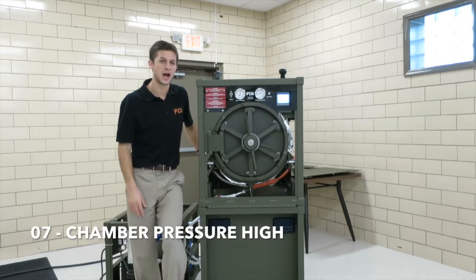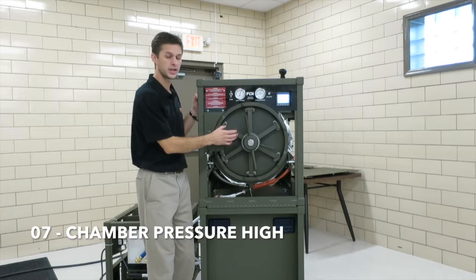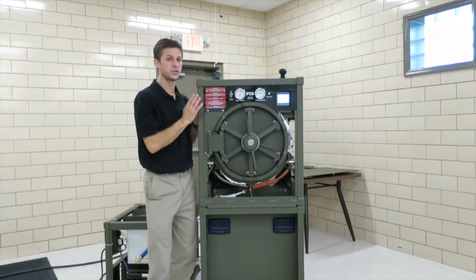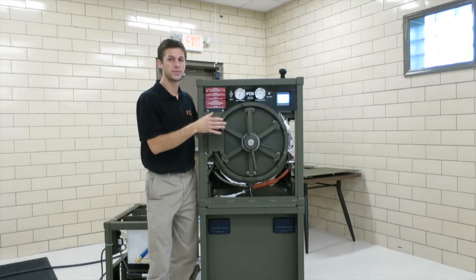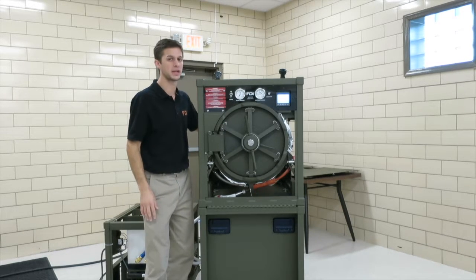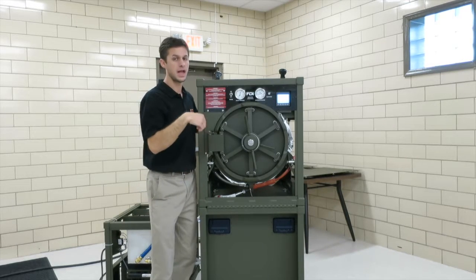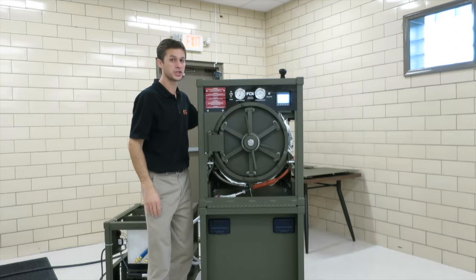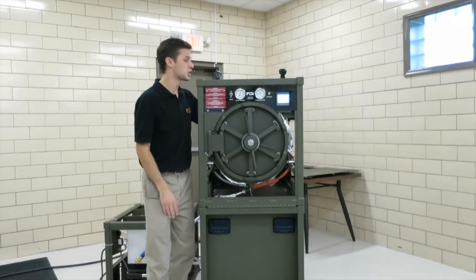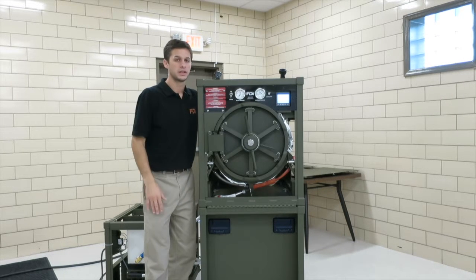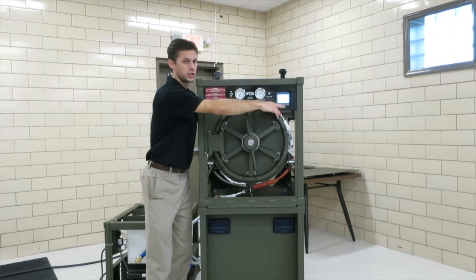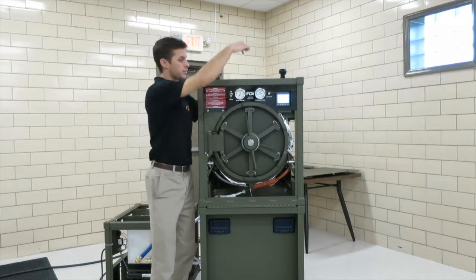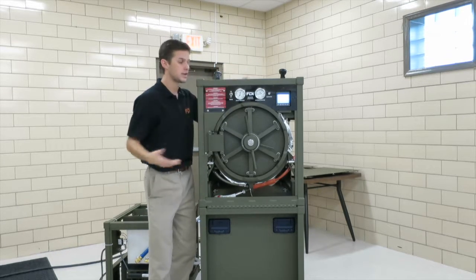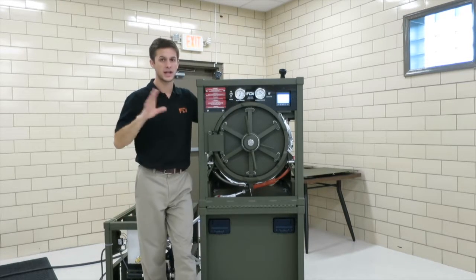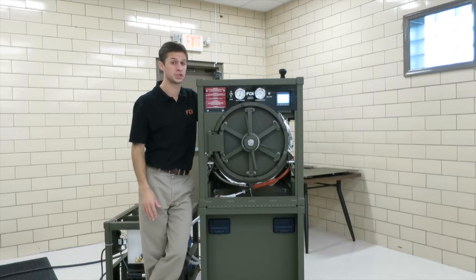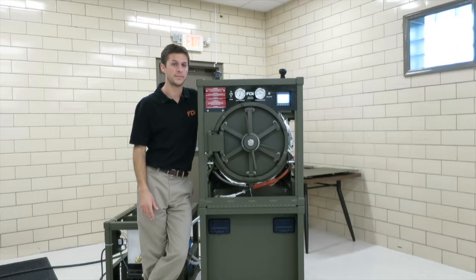Number 7 is the chamber pressure high. This one, since the chamber is connected to the jacket, we're going to reference you to jacket pressure high 09. Anytime the chamber would be over pressure, it'd be caused by the jacket being over pressured, since the steam in the jacket enters into the chamber. There is the chamber pressure sensor on top though that's reading that pressure. And so if it happened to malfunction and maybe spiked in its pressure output reading to the PLC, you could get this alarm. So you have your chamber pressure transmitter here on top that could malfunction. Very durable, should last a very long time, but if that got bumped, maybe damaged during transport, you could potentially get a chamber pressure high alarm 07.